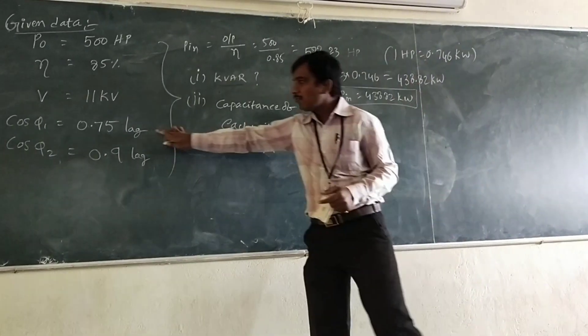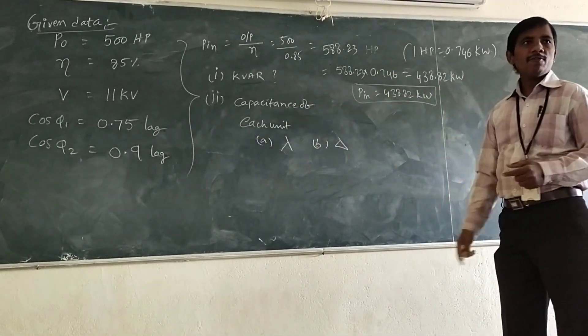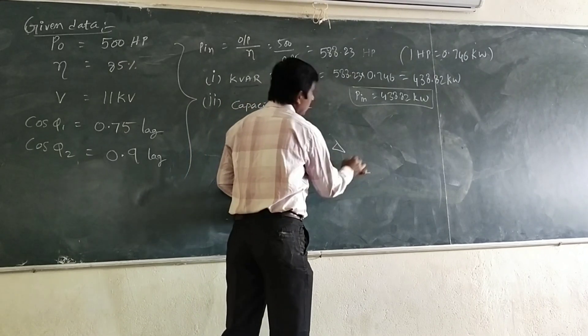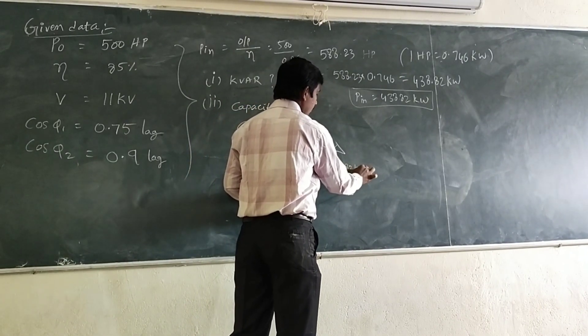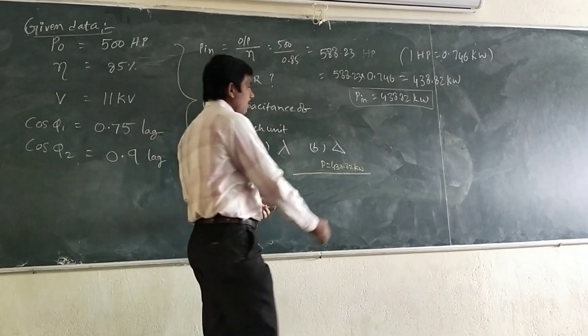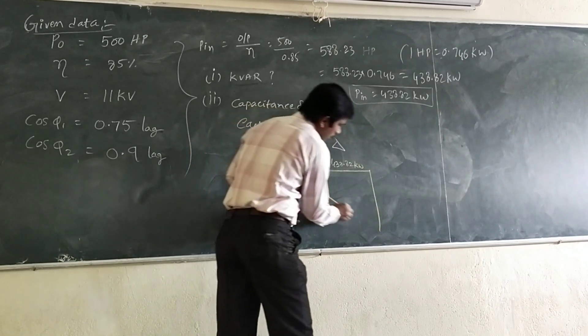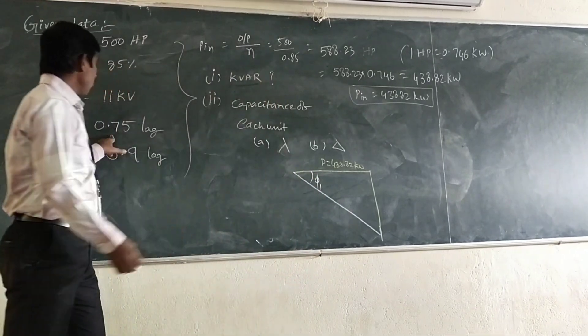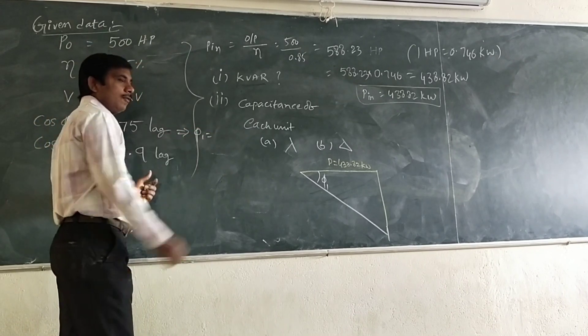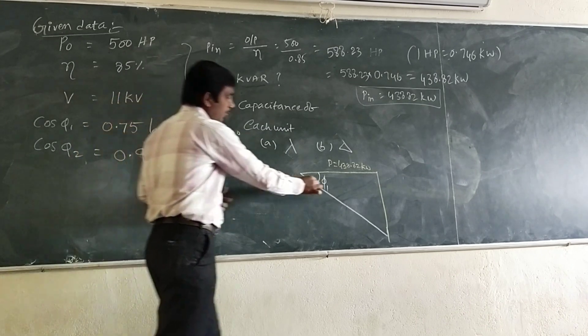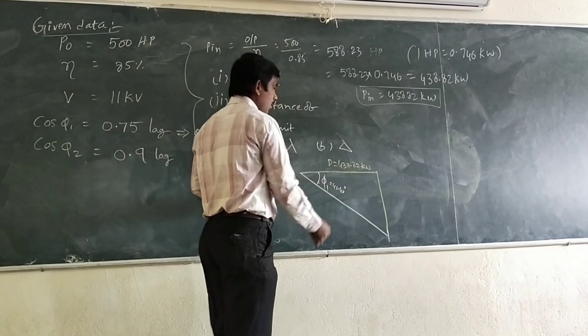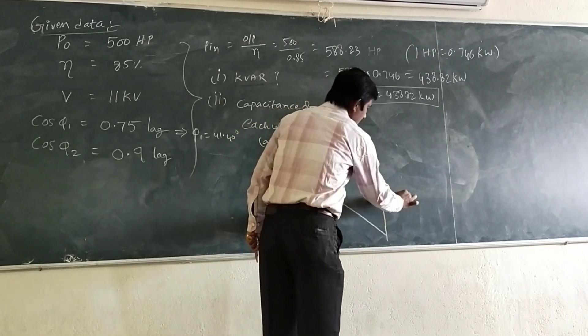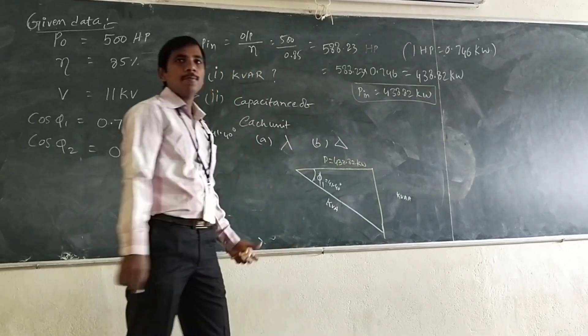To improve the power factor from φ₁ to φ₂, we use the formula: P × (tanφ₁ − tanφ₂). Drawing the power triangle: P equals 438.82 kW. The initial power factor cosφ₁ equals 0.75, so φ₁ equals 41.40 degrees. The improved power factor cosφ₂ equals 0.9, so φ₂ equals 25.84 degrees. The power triangle has sides P (kW), kVA, and kVAR.